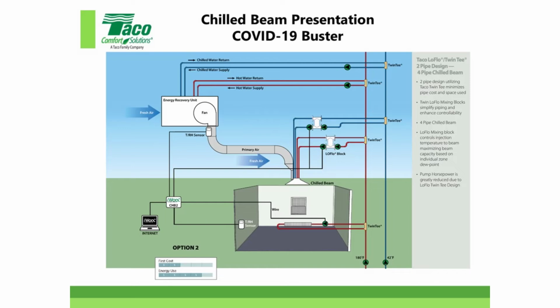It goes out at 42, but when it gets over to here, it's 58, at least a few degrees. We do it 5 degrees, but other people do it less, above the dew point, and then you've got connections running out to the energy recovery unit for the coils in there as well. So that's a potential savings. Oops, I went back. Right, you start doing piping, right? I mean, if we have a contractor in our group, you know how much you charge per foot of pipe or whatnot. You can see some of the savings here when you look at this low flow type of system.